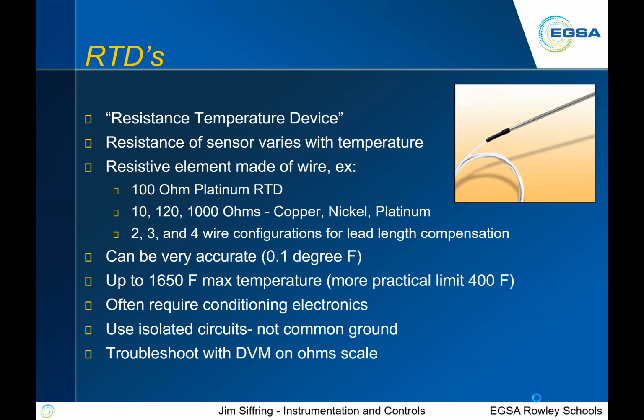You might see these with 2 wires, you might see them with 3 wires, you might see 4 wires. Typically, the 2 wires, if you've got a device that's very close to the instrument that's reading it, then you don't need the 3 and 4 wire configurations. The 3 and 4 wire configurations mainly are there for lead length compensation. So they can be quite accurate. You can go up into pretty high temperatures. You almost always have to use some kind of conditioning electronics to give you some sort of a readable output. And you have to have isolated circuits on these, so no common grounds. Again, troubleshoot it with a multimeter on ohms. If you get some sort of resistance, it's probably okay. If you don't have any kind of resistance, or it's way high or something like that, you might have a problem.